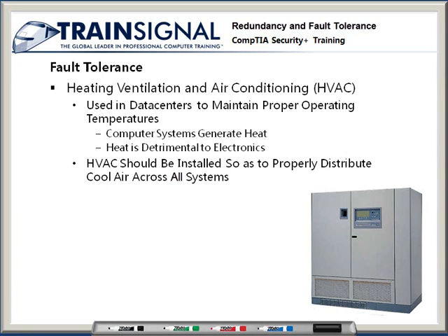I can't tell you how many times I've walked into a data center where at first glance I think, this is cool, it's chilly, everything seems to be running just fine, and I walk down a few rows and all of a sudden, bam, it's super hot in that area. And I realize that they have enough cooling, they have the capacity to cool everything, but for some reason they're not getting the cool air to this area of the data center.